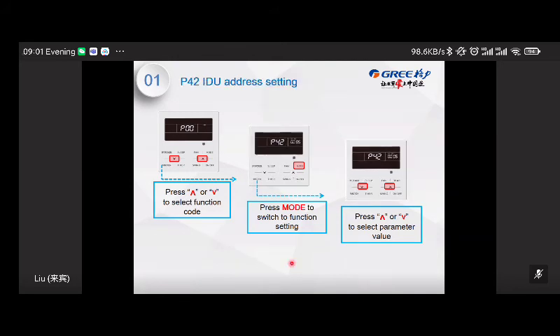Next one, P42, indoor unit address setting. At the beginning of commissioning, the address of every indoor unit is set automatically. They are random. However, maybe you want to change the address for each indoor unit, you can use this code P42 to change the address of that indoor unit. Okay. And also sometimes if the address conflicts in your VRF system, you can also use this one to clear the address conflict.